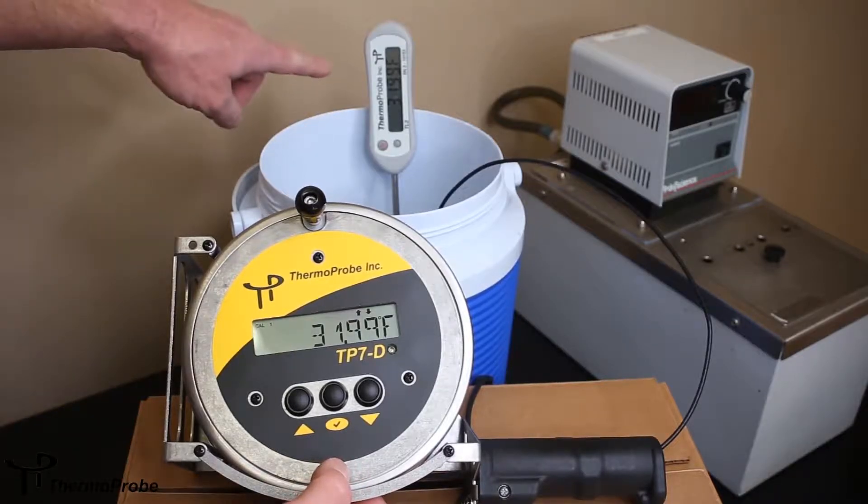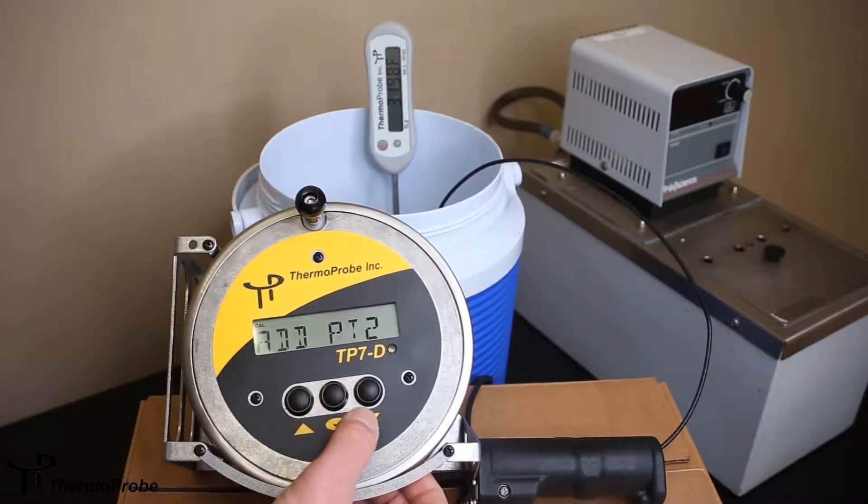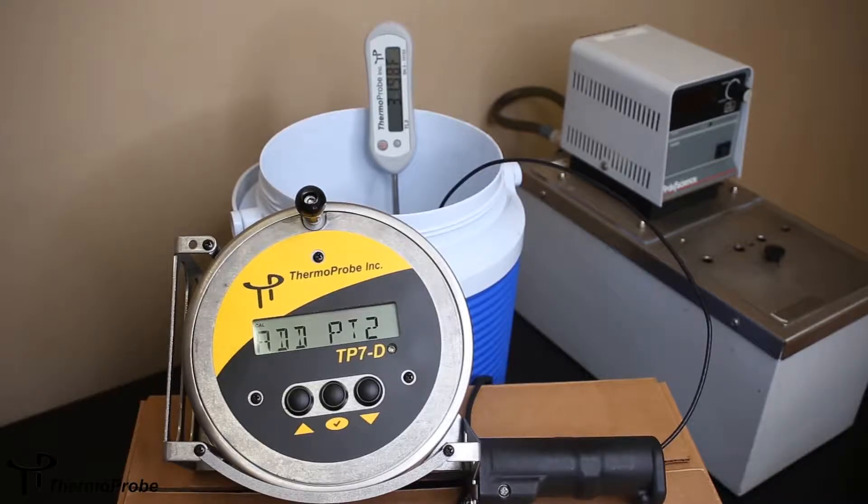Once the two match, so both are 31.99, you hit select. It asks if you want to save. You hit select again to confirm, and now it shows that we want to move on to point two.